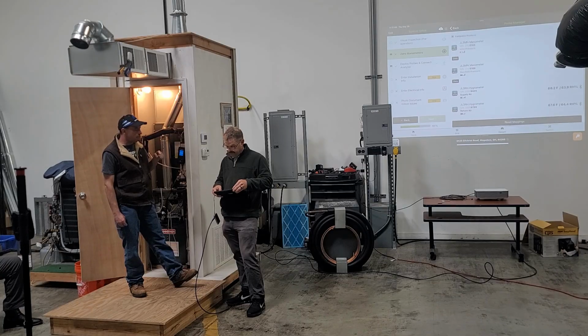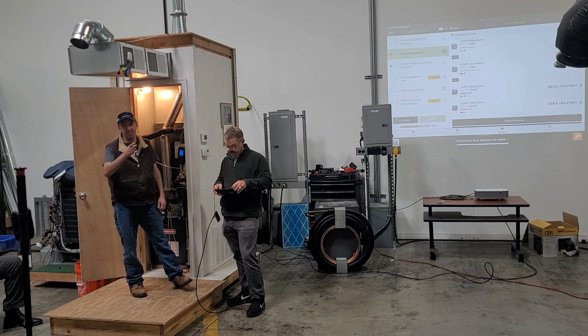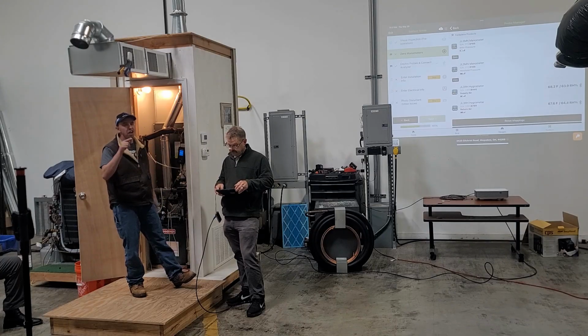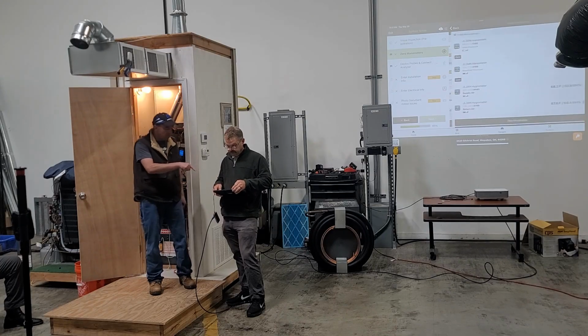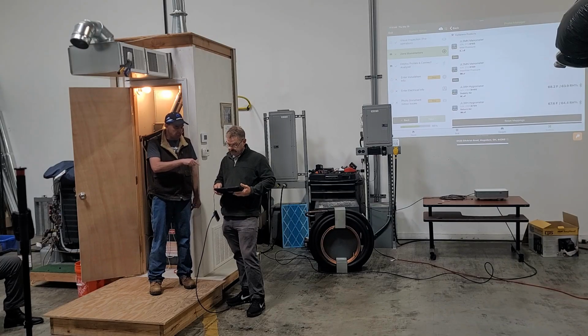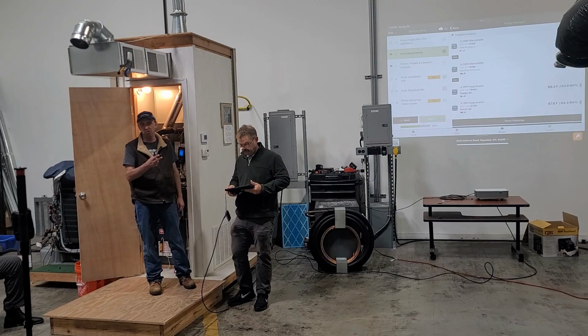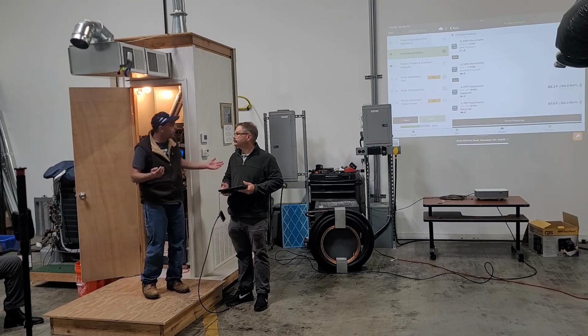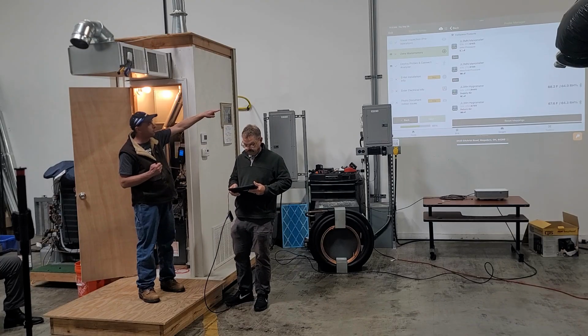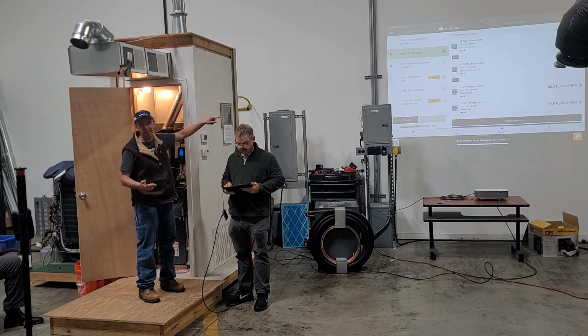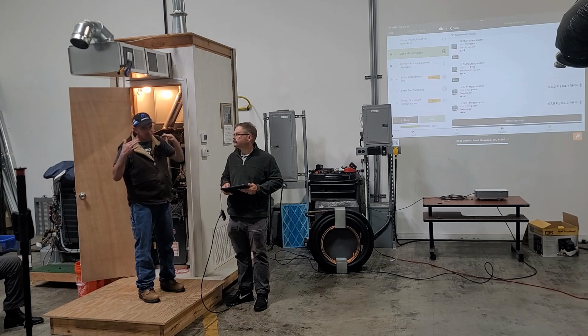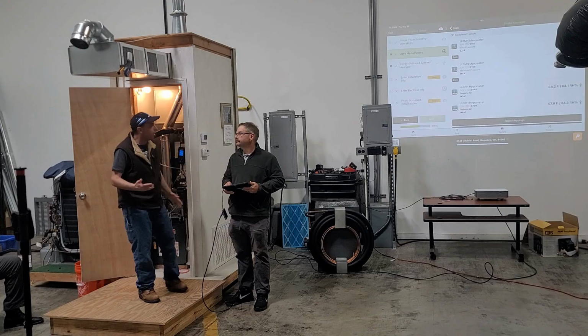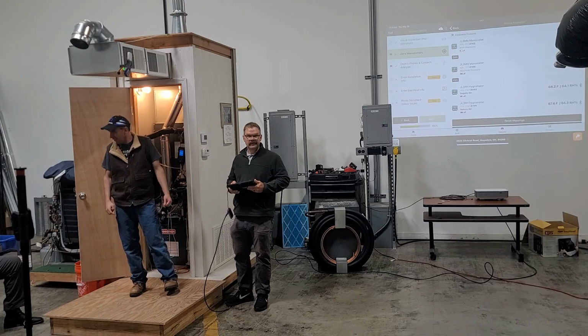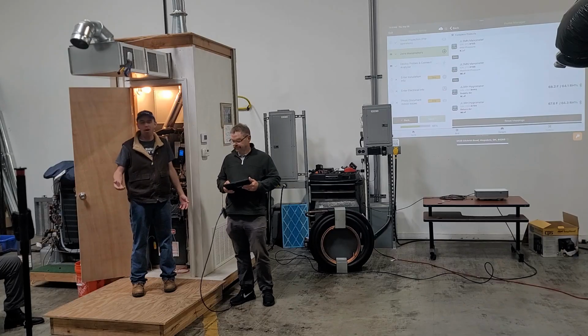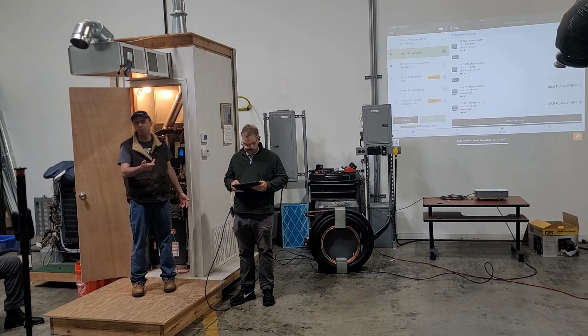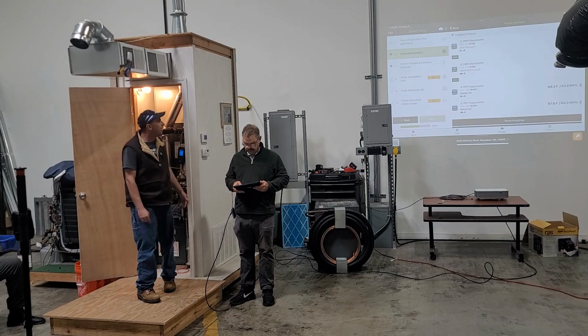Another thing for you guys, and you know, this is my OCD - you have different probes. What I do with my probes is usually the serial numbers are sequential on two of the probes, and maybe this will help you, but I always pick my low serial number as the low side, or the suction line. There's a little mental system that I have, that's my system, definitely the lower number. And then the oddball psychrometer on the cooling side, the oddball psychrometer is outdoor. So that's how I do it.